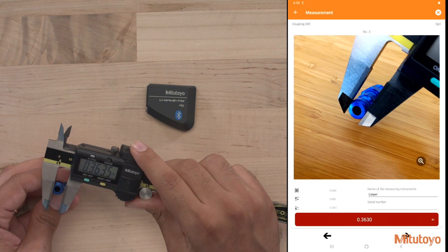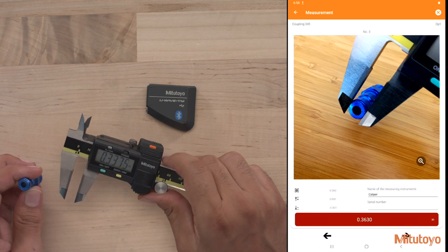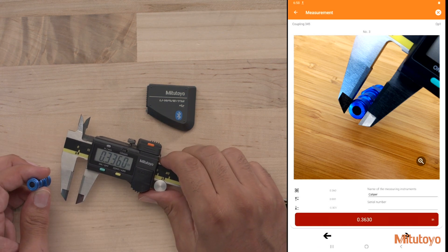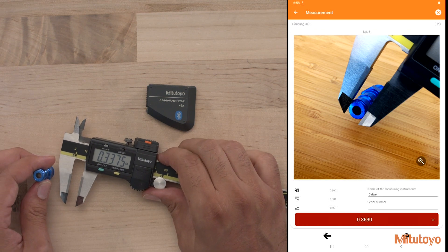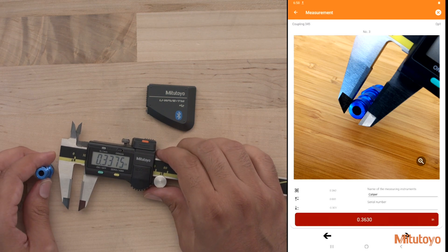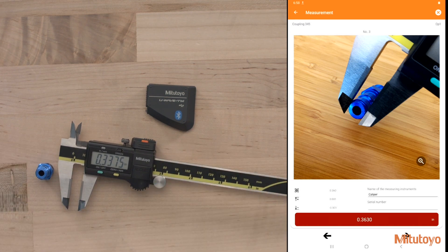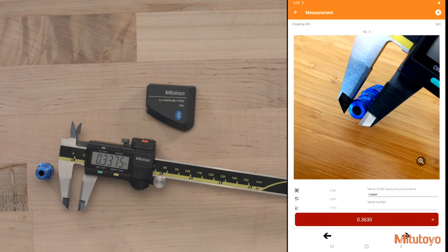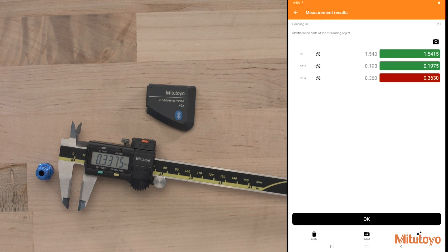And here we can see this part. And this characteristic is out of spec. I can go ahead and do a retake if I need to, maybe I took it incorrectly. Or I can go ahead and hit the arrow button to move on through to finish through my navigation.